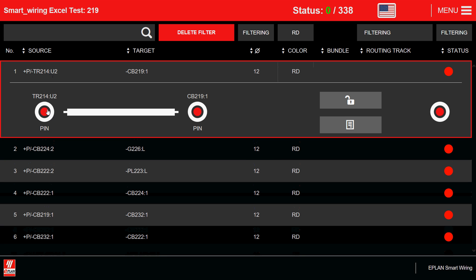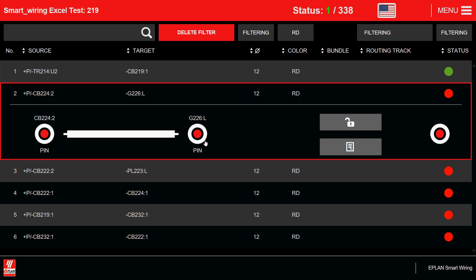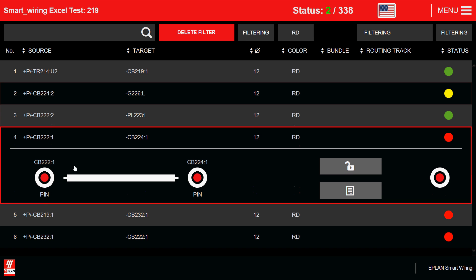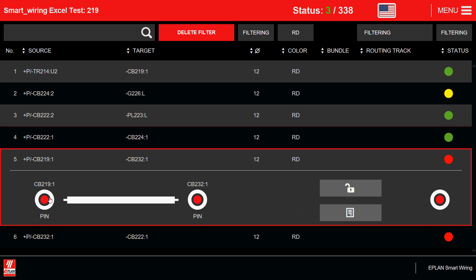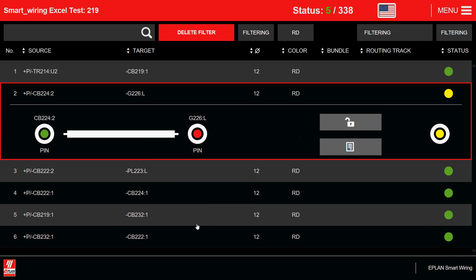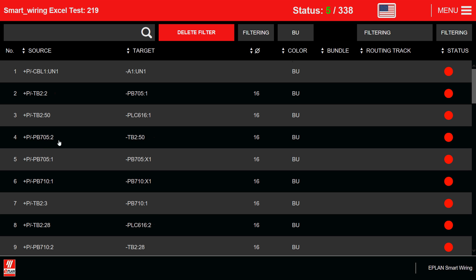I can actually filter for specific colors. Let's say here are the red wires. And if I start by wiring something, the status turns into green, which means it's installed. Or if I only install on one side, it's partially installed. So I can basically install the wires as we go on. And when I'm done with the filter, it moves back onto the partially installed. If I want to go back, I can lock that wire for the moment. I can go back and eliminate the filtering. Go back to maybe the blue wires or the black wires in a certain size.